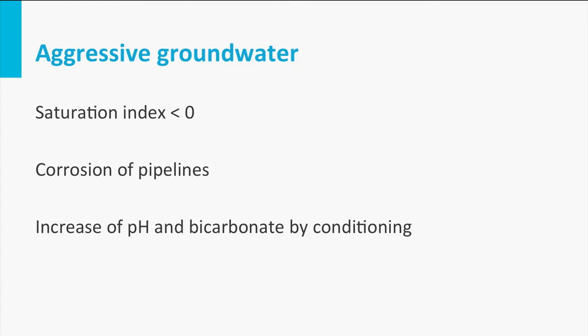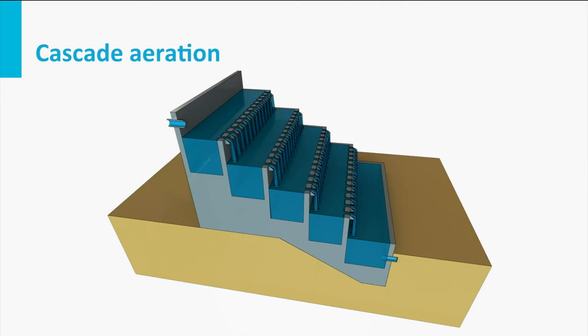This is caused by subsurface breakdown processes resulting in carbon dioxide in the water above the equilibrium concentration. With the saturation index (SI) below zero, the water can corrode the pipelines during distribution. The SI can be increased through aeration, but because of low bicarbonate concentrations, it may still be recommendable to apply a conditioning step, such as limestone filtration.